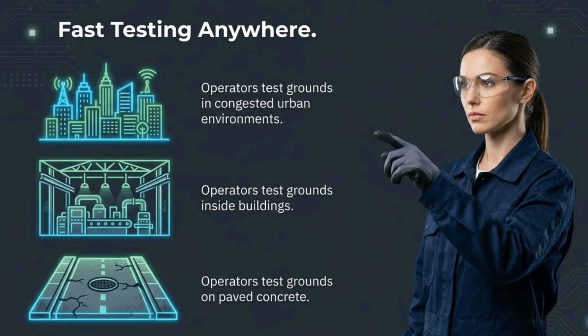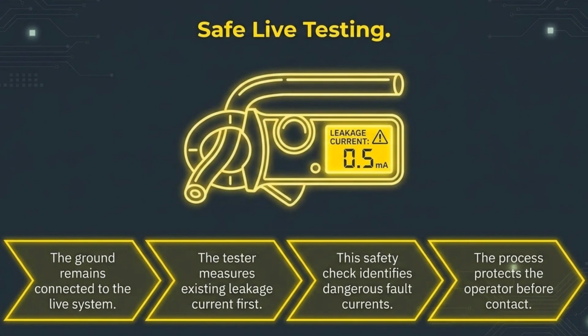This versatility allows operators to perform fast testing in various environments, including congested urban areas, inside buildings, or on paved concrete surfaces. The process is designed for safe live testing. By measuring existing leakage current first, the tester identifies potential faults and protects the operator before any further contact.